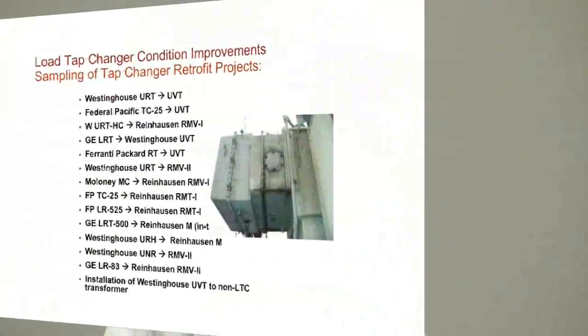You have the reduced downtime. If you're not taking the unit off the pad, moving it to a customer repair location, you have that time frame that's much, much shorter on site. Like I say, typically a retrofit in most cases will run anywhere from 2 to 4 weeks. 2 for a normal tap changer where we can unbolt one, weld another one on, bolt it on. If we have to do a lot of modifications, adding PAs, or just changing the whole design of the board, have the leads route through, it can get up to 4 weeks in time.